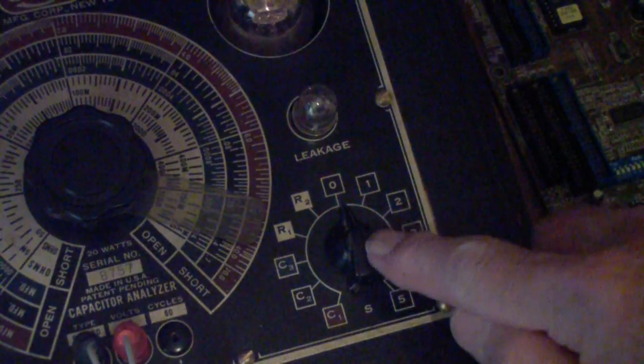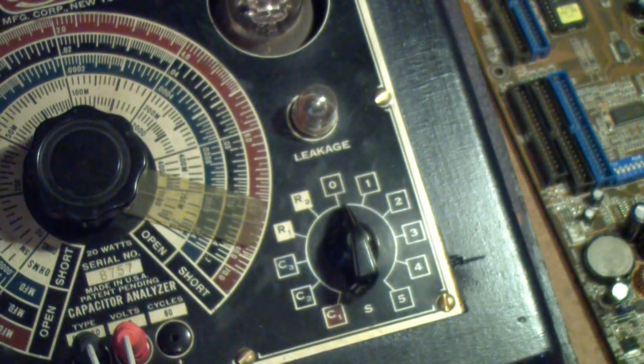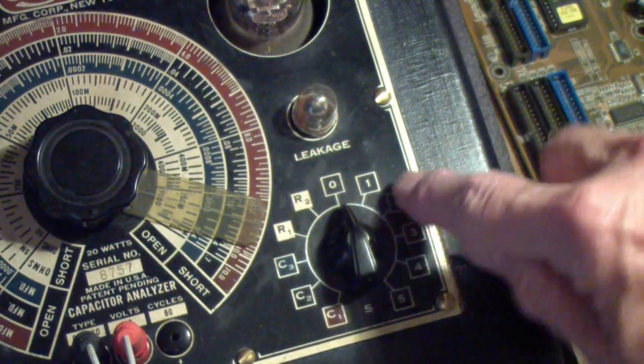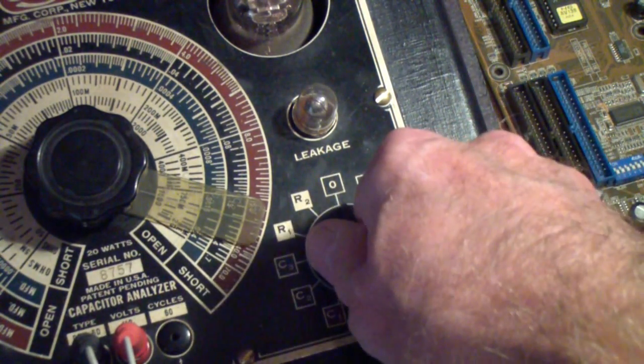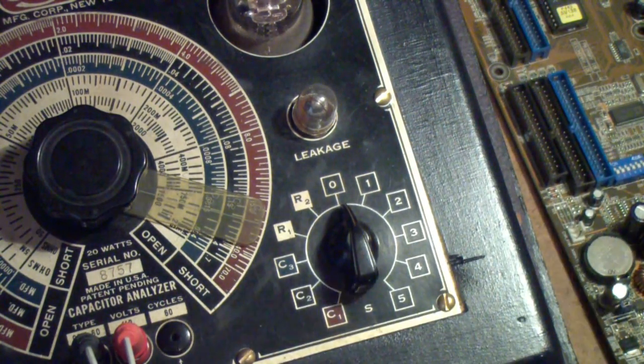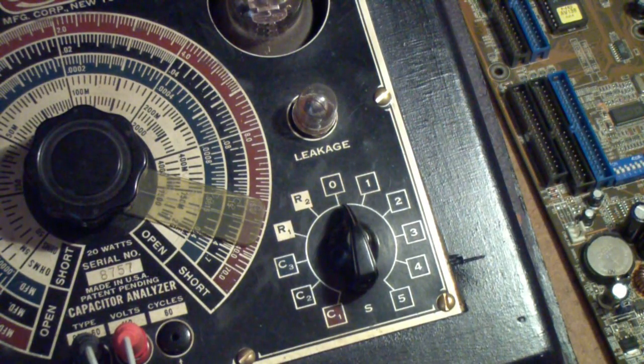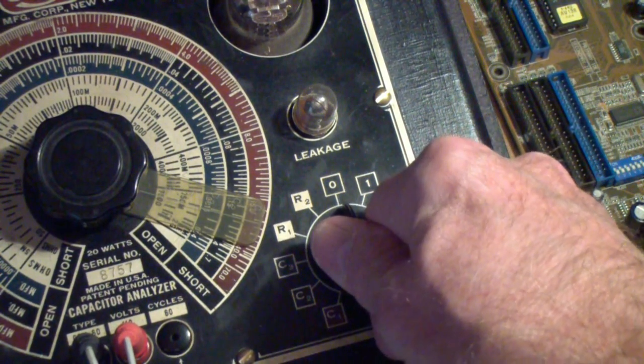What I've now done is move the switch over, and I think I can turn the light back on for this because this is a little bit brighter bulb. It's set to the zero position. That means that the leads are shorted, and we'll talk about these leads in a second. The first position tests at approximately 100 volts, and I say approximately because these testers weren't really calibrated that well, but around 100 volts maybe plus or minus 10.